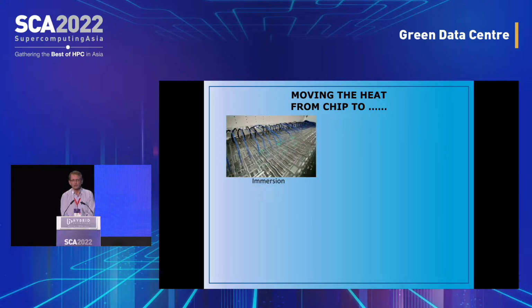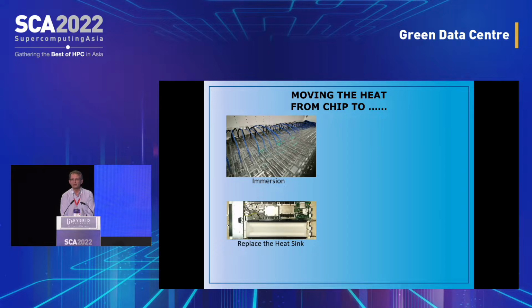How could we actually take away the heat from the chip and take it completely outside of the data center, without using airflow, without using that insulator? There are a few ways we could do that. We could use immersion-style liquid cooling, putting the servers, the IT equipment, into a bathtub full of some liquid - that's immersion. Or we could replace the heat sink with a different kind that has liquid flowing through it to more effectively take away the heat.